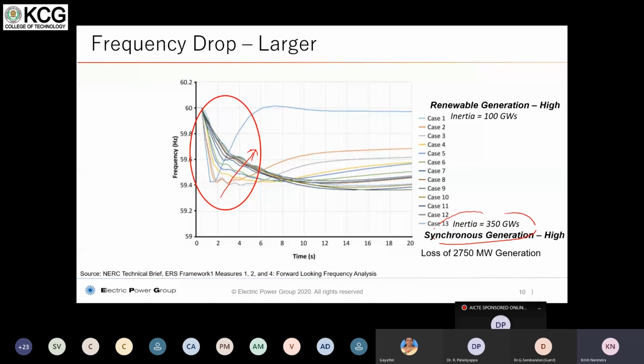Now, when the inertia comes down because the renewables are going high, look at the way the traces are coming down on the rate of change of frequency. It goes very high, and the frequency will drop to a much lower value. Because of this, there's a danger in the system, and therefore the frequency should never drop below a certain limit, as planned or as regulated in a system. This depends on the system, basically. So monitoring these things in real time is an important aspect, as I said, because of the variability in generation, and because inertial support is not available from the renewables.